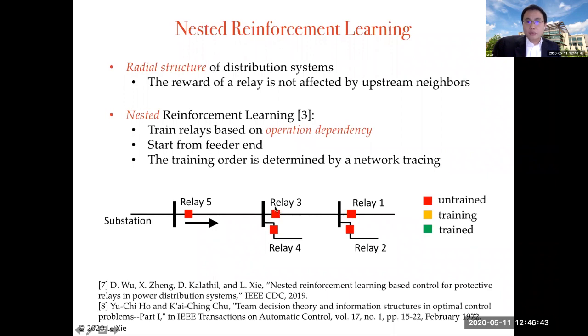The converse is not true. Namely, how well relay 3's decision is rewarded actually depends on the state of relay 1. Because if your downstream is still energized, you better be careful, right? You have a different kind of decision versus if your downstream relay 1 is de-energized.